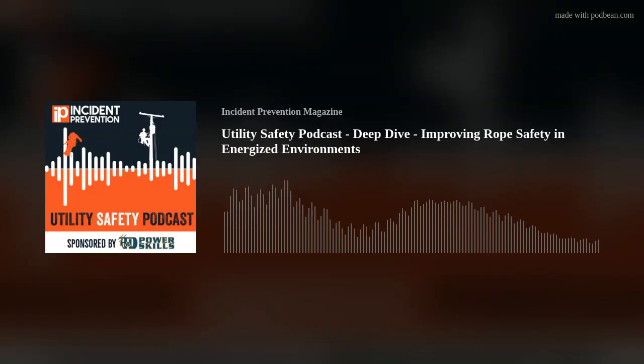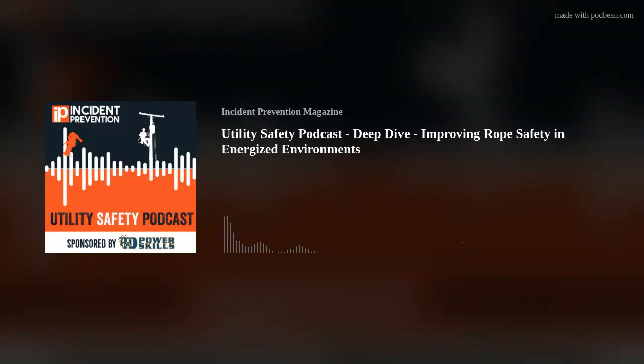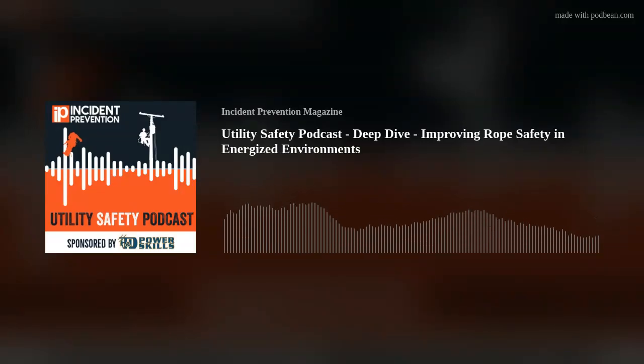Barrier number two is really dangerous: the assumption we always work de-energized. But things aren't always truly de-energized. That thinking ignores so many risks: induction from nearby lines, accidental re-energization from a switching error or lightning, even customers backfeeding the grid with improperly wired generators during an outage. We've seen cases where ropes became energized during what everyone thought was dead work. The only truly safe approach is to treat every system as potentially live, because the consequences of being wrong are too severe.